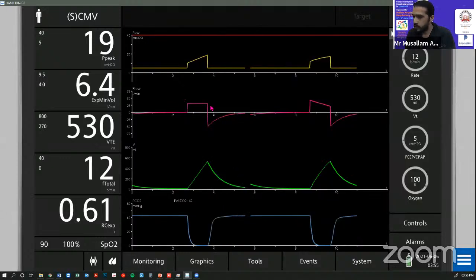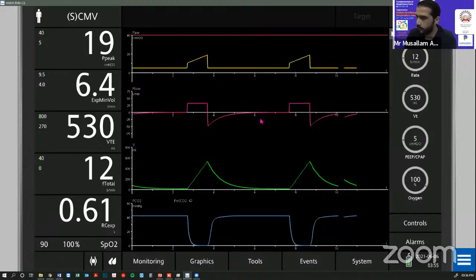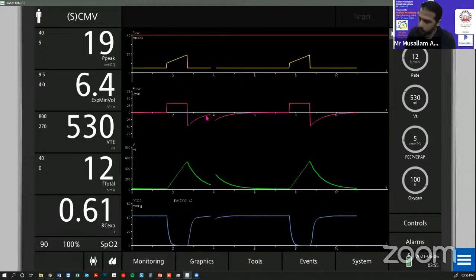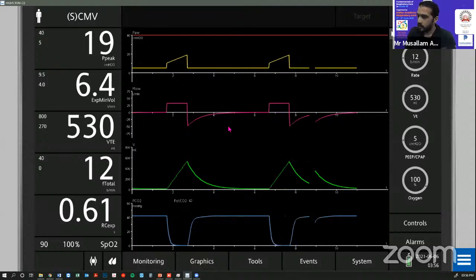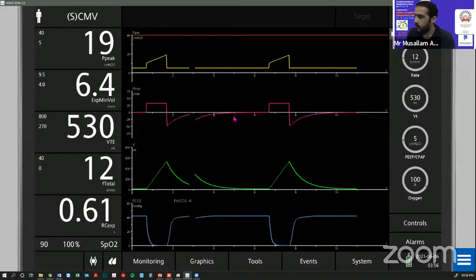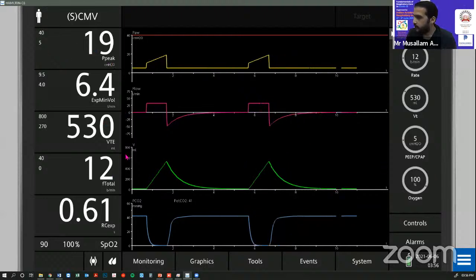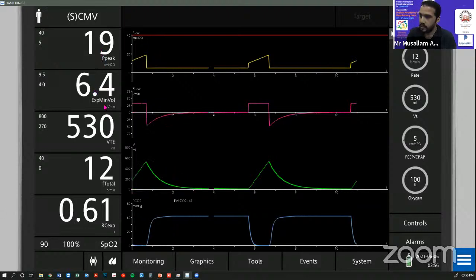flow. So usually volume control has a square waveform for the flow, and we can tell a lot from here. We can know a lot of problems from the flow-time waveform. I will show you, inshallah, those problems in the last simulator, which has the most smart features. So this is basically how it looks, and this is the measurement of the patient, how much is his peak pressure and how much is the minute volume or minute ventilation that the patient has.